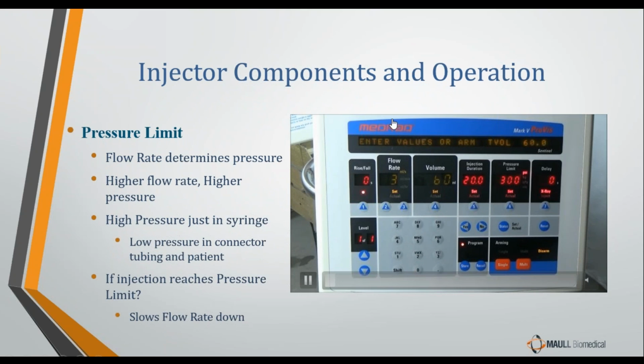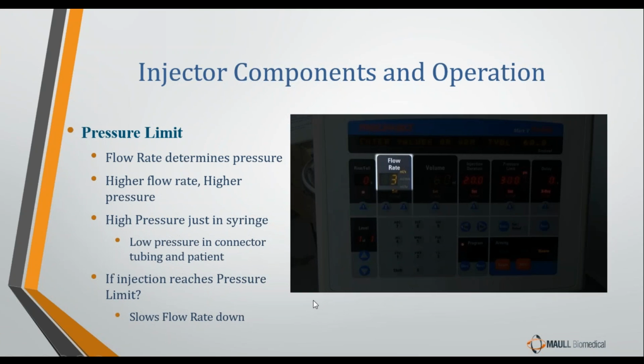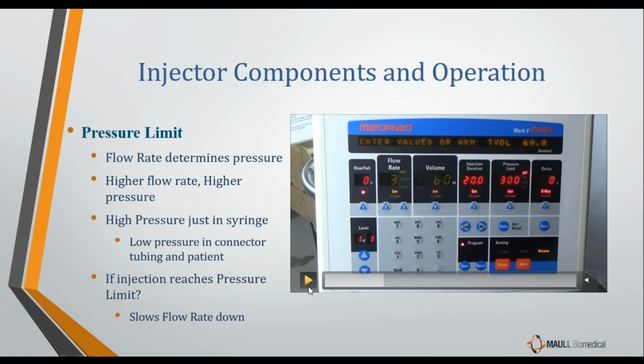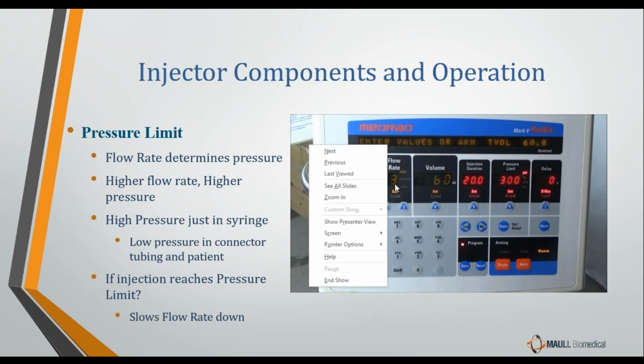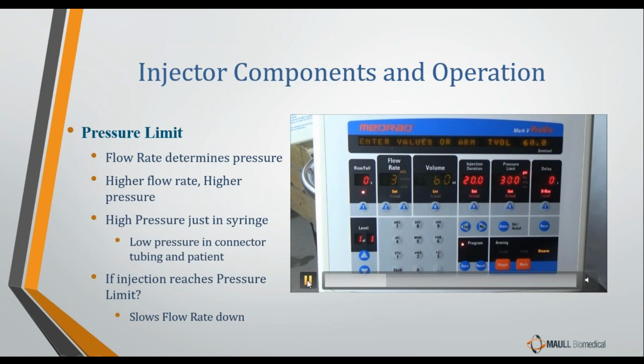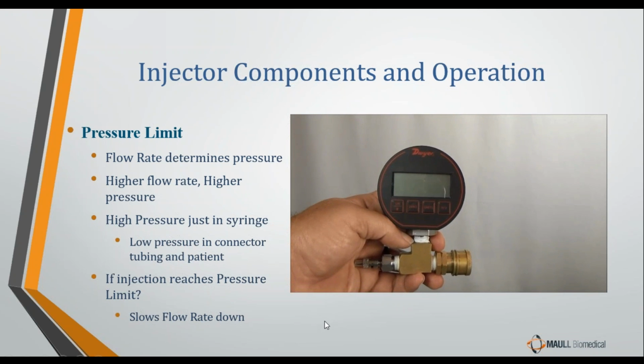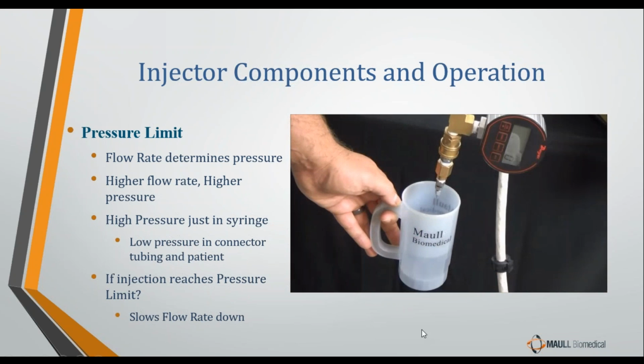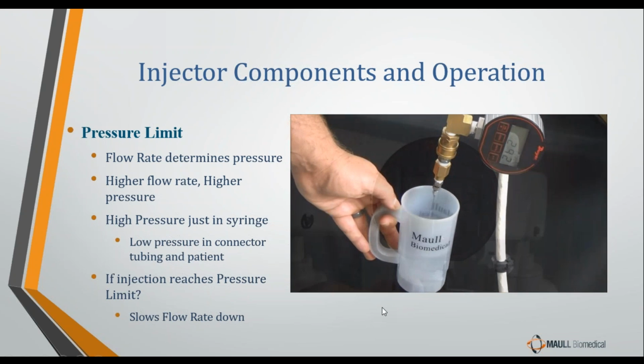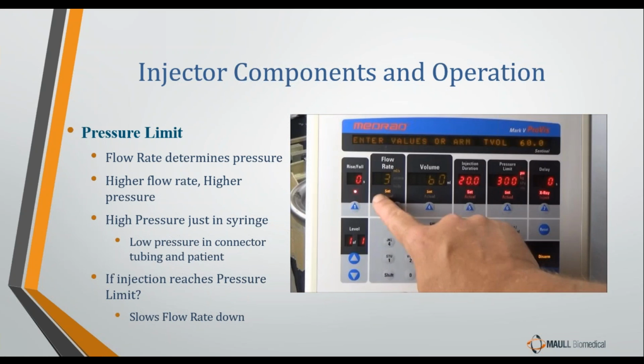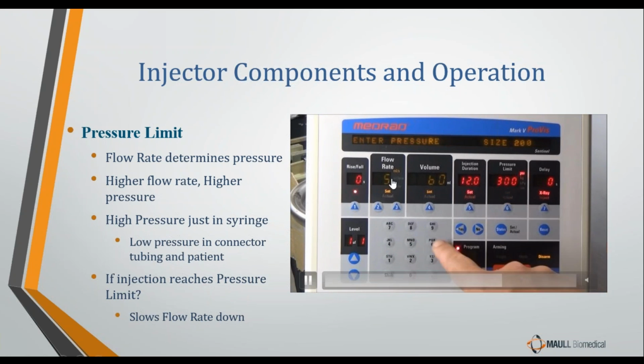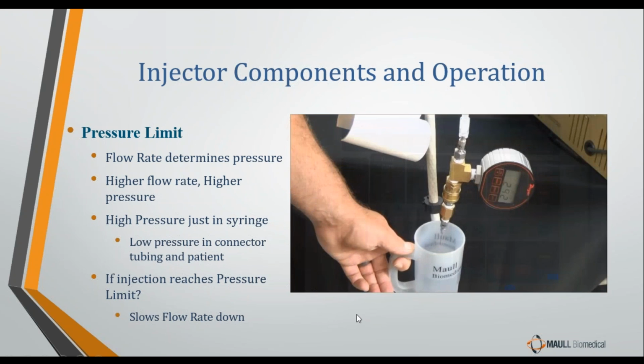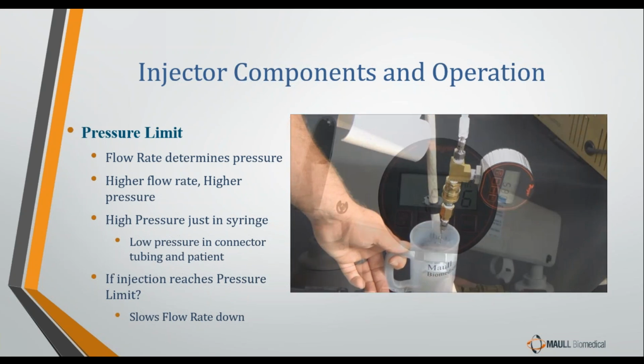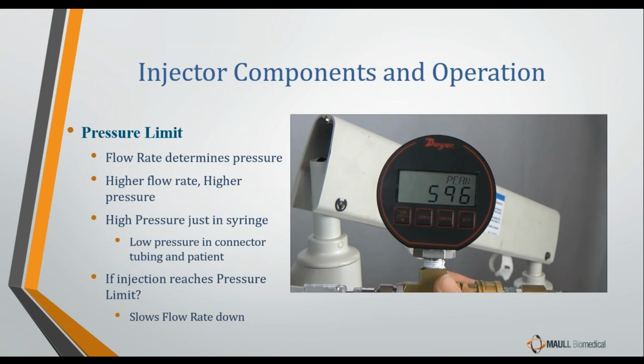Now, the primary determinant of how much pressure gets built up in a syringe during the actual injection is the flow rate. There are several other things that affect how much pressure gets built up in a syringe, but the primary determinant is the speed of the injection, the flow rate. If you look here, we program a flow rate of 3 milliliters per second. During our test, we inject the fluid through a fixed size orifice, a needle valve or some other orifice. A 3 milliliter per second flow rate through that needle gives us, in this case, a pressure of 292 psi. Now, if we up the flow rate to 5 milliliters per second through that same needle valve, you see we get a pressure of 596 psi.